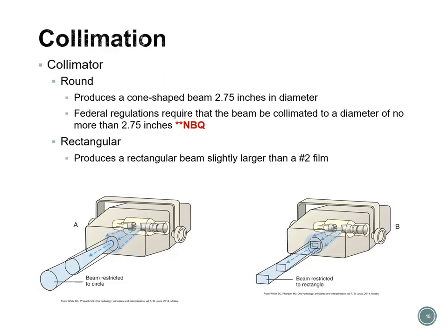Both a round collimator and a rectangular collimator are visible here, and you can see the difference in the beam shape each produces. The collimator is located between the tube and the PID. The circular or round collimator produces a cone-shaped beam 2.75 inches in diameter—federal regulations require that the beam be collimated to a diameter of no more than 2.75 inches. The rectangular collimator produces a beam slightly larger than a number 2 size film.